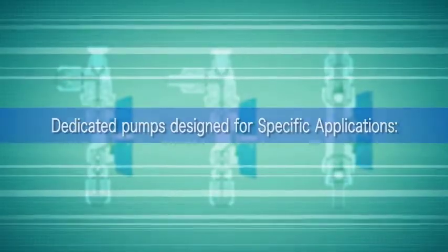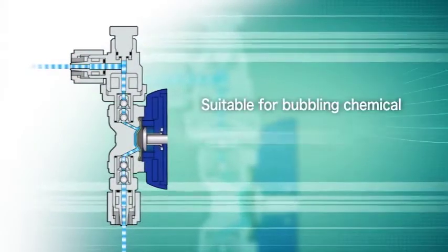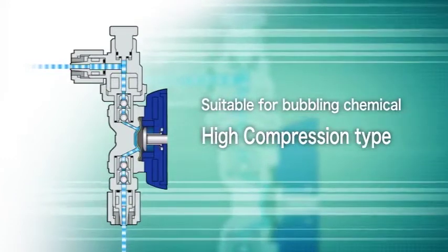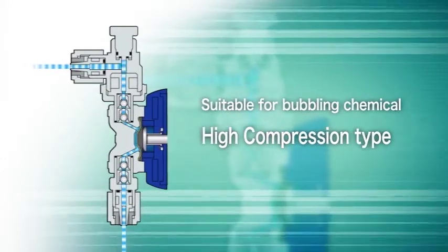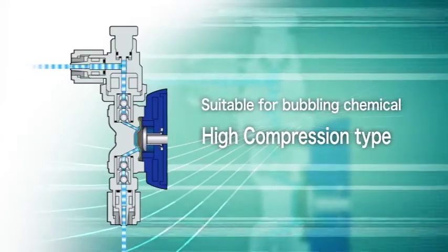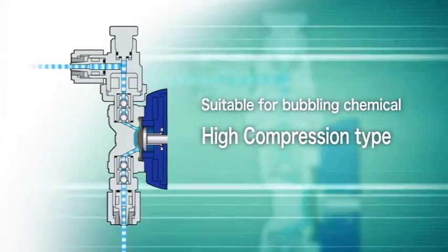The high compression pumps were designed for chemicals that outgas, such as sodium hypochlorite. Increasing volume per stroke and decreasing dead volume increases the compression ratio, making a pump design excellent for pumping chemicals that contain a lot of gas.